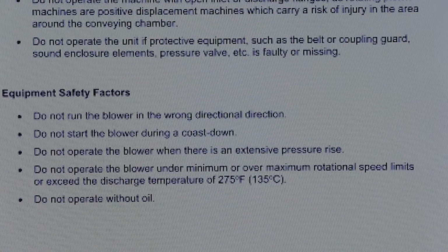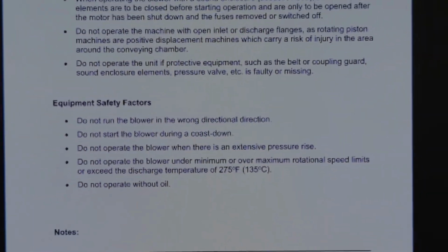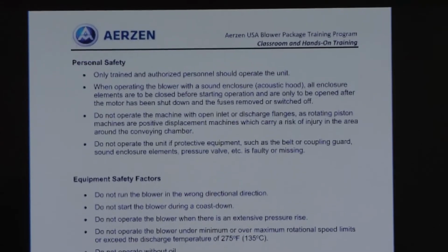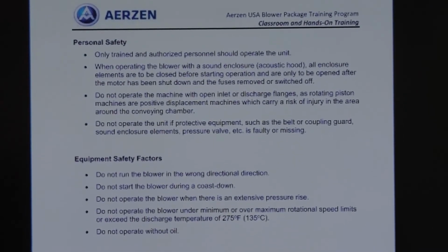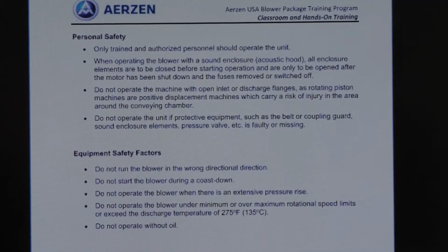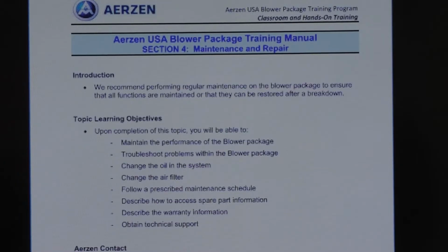Because on those slingers that I discussed, they're a round disc and they have a notch that's designed to turn the one way to pick the oil up and sling it throughout the housing. If you turn it backwards, then it's not getting lubricated. You're pulling against the check valve in the blower, and bad things can happen. So you always want to make sure that it's turning in the right direction, and I'll show y'all physically on the machine where it gives you the arrow and which way it turns. Go ahead and go to the next one.